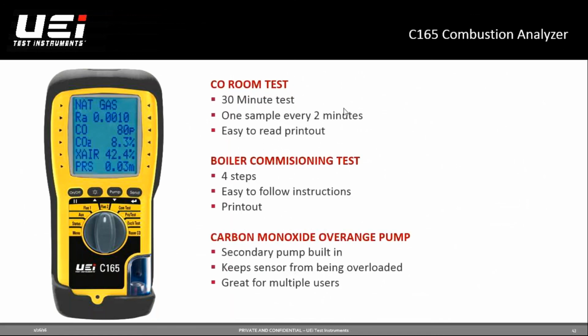As I said, these are the tests it'll do - the CO room test, the boiler commissioning test, and that carbon monoxide overrange pump, which I can't tell you enough about how life-saving, time-saving, and unit-saving that has been for our contractors.